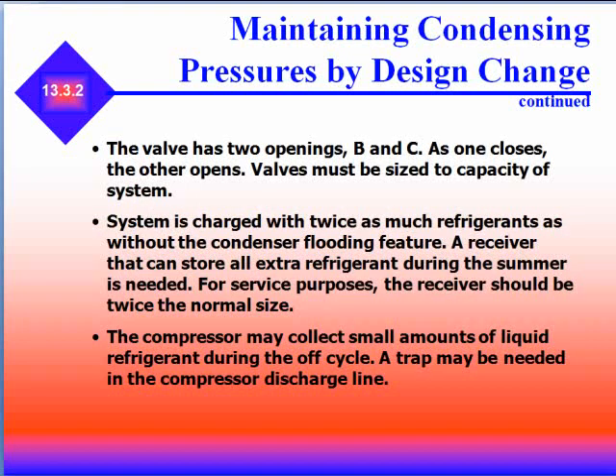The valve has two openings, B and C. As one closes, the other opens. The valve must be sized to the capacity of the system. The system is charged with twice as much refrigerant without the condenser flooding feature. A receiver that stores extra refrigerant due to summer conditions is needed, and for service purposes, the receiver should be twice the normal size. The compressor may collect small amounts of liquid refrigerant during the off cycle, and a trap may be needed in the compressor discharge line.